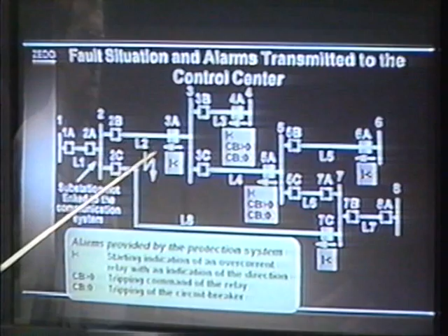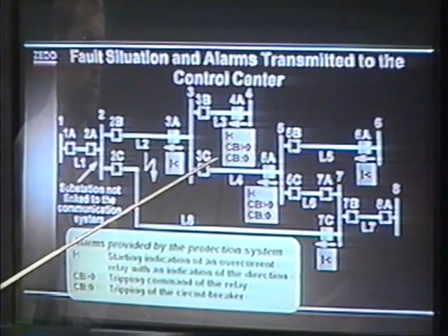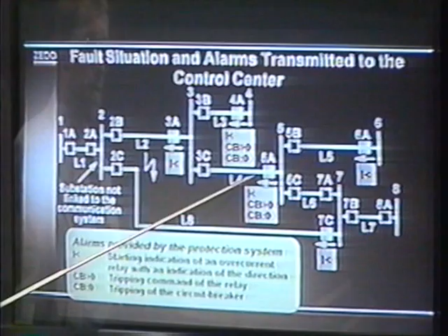detects the overcurrent, but it fails to submit the switching command to the related circuit breaker, so the backup protection devices have to switch off the fault on line L2. These backup protection devices are located at bus bar 4, feeder A, where we can see that the overcurrent detection alarm was generated, the circuit breaker tripping command was generated, and the message that the circuit breaker really tripped are available in the central control center as well. The same information we have from bus bar 5, feeder A, where the circuit breaker was tripped as well.